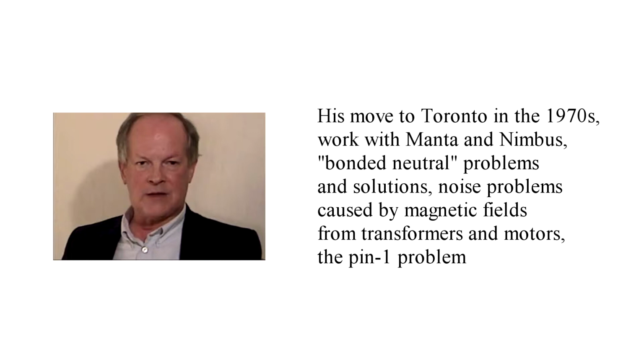It was the H field around the wire due to the neutral current. That introduced me to the concept of neutral bonds, which is the biggest deal there is when tracking down interference in a building. It takes one bonded neutral anywhere in the building—if it's a steel frame, which most are, you get H field everywhere. That's the magnetic field; E field is electric.